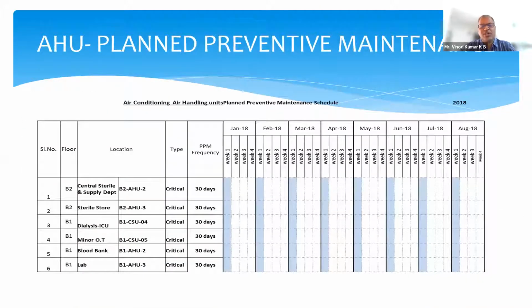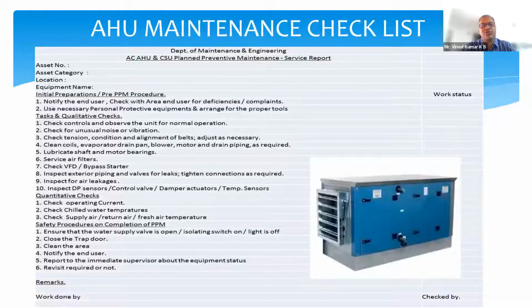So you need to have planned preventive maintenance for the whole year for all your theater AHUs and ICUs. Then you should have a proper checklist, which you actually utilize every time. Whenever the maintenance is being done, all these points are supposed to be checked and monitored, so that the AHU doesn't fail or give lower performance, and you avoid problems with cooling, air filtration, or even positive pressure inside your theater. So please maintain this checklist when the technician visits the AHU every month, and make sure that he checks everything on the AHU.